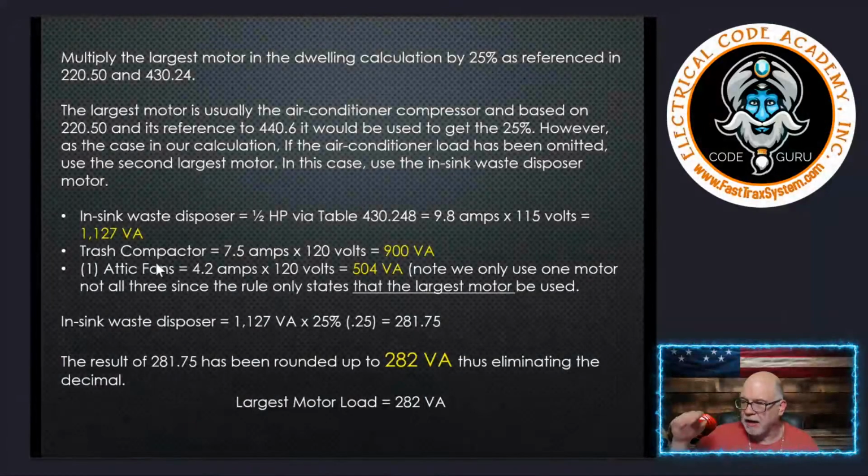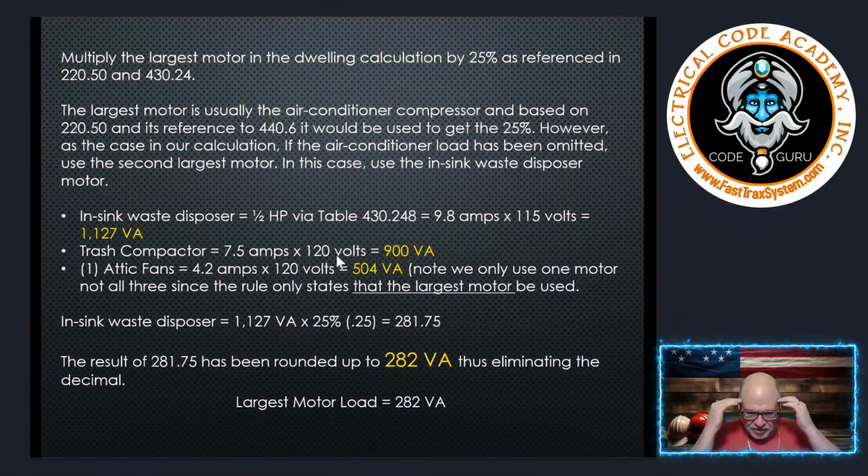All right, now, in our case, this is where you got to think. Remember when we did the AC, which is the largest motor in the building, that air conditioning compressor? But we compared AC versus heat, right? Well, guess what we did to that AC load? We got rid of it. We threw it away. We kept the heat. So we're not going to go after that air conditioning motor now. We have to now go for the next largest motor.